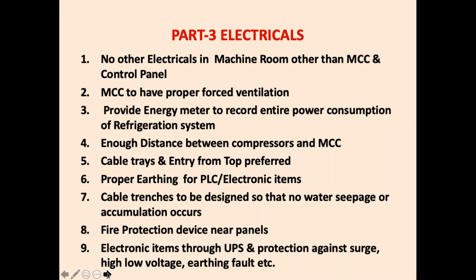Provide an energy meter to record the entire power consumption of the refrigeration system. This I have rarely seen in any refrigeration plant. If I ask operators, they say the compressor draws this many amperes, the fan draws this many amperes, the pump this many. I say, "Arre baba, how much total power do you need?" They say, "No sir, we don't have a meter." So a total energy meter is very, very important.